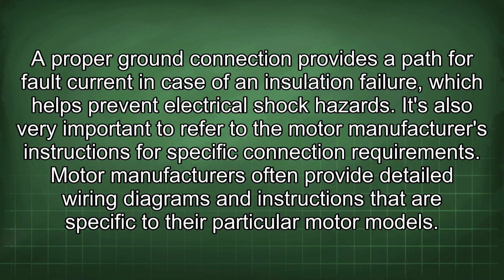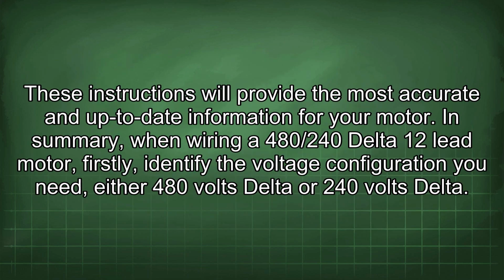A proper ground connection provides a path for fault current in case of an insulation failure, which helps prevent electrical shock hazards. It's also very important to refer to the motor manufacturer's instructions for specific connection requirements. Motor manufacturers often provide detailed wiring diagrams and instructions that are specific to their particular motor models. These instructions will provide the most accurate and up-to-date information for your motor.